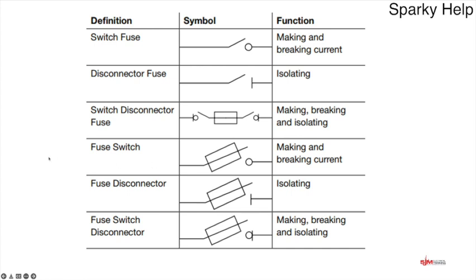The difference between the two: in a switch fuse, you actually switch the switch and the fuse is beyond it typically. Or you have a fuse switch where the fuse is actually in the switch. The bit where this differentiates between the different types, as we've got down on the function on the right-hand side, the manufacturers make different versions of each of their switches, and it's down to you as the designer, installer, or selector to make sure you put the correct one in the correct location.